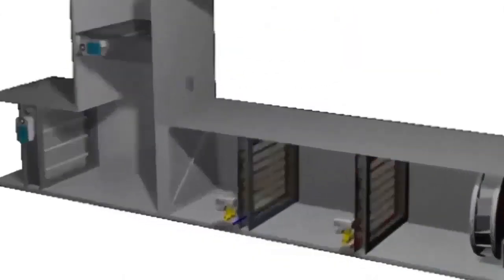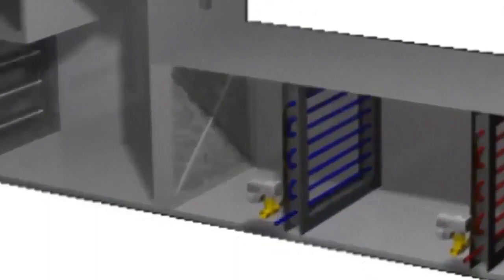After the dampers, there are filters to trap all dirt and dust, and at each filter bank, there will be a pressure sensor that measures the dirt on the filters, and alerts when they need to be replaced.